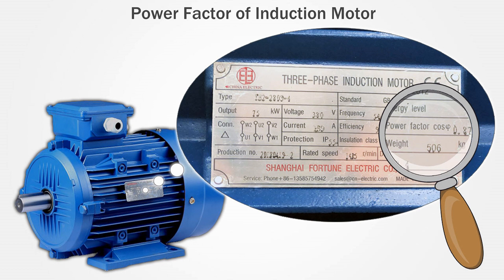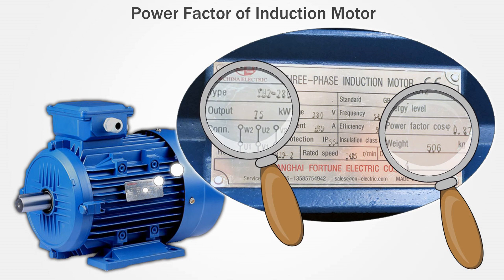Let's get back to our induction motor and take a closer look at the motor nameplate. As we can see, this induction motor has a power factor of 0.87. We know the power factor is a variable value. As power factor varies with load, the nameplate power factor is at full motor load. For example, the power factor of this motor is 0.87 with the rated output of 75 kilowatts.